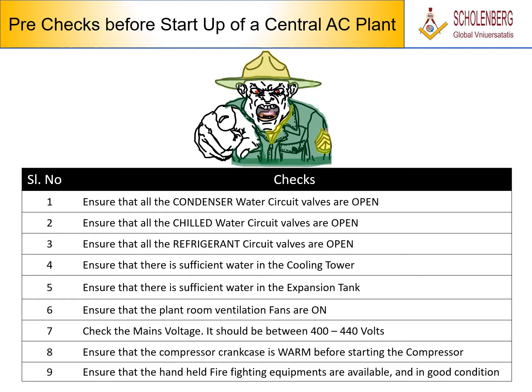6. Ensure that the plant room ventilation fans are on. 7. Check the mains voltage. It should be between 400 to 440 volts. 8. Ensure that the compressor crankcase is warm before starting the compressor. 9. Ensure that the handheld firefighting equipments are available, and in good condition.